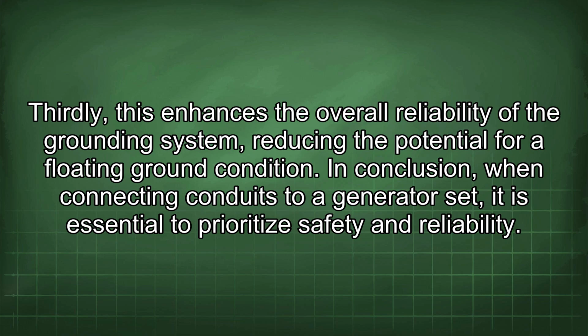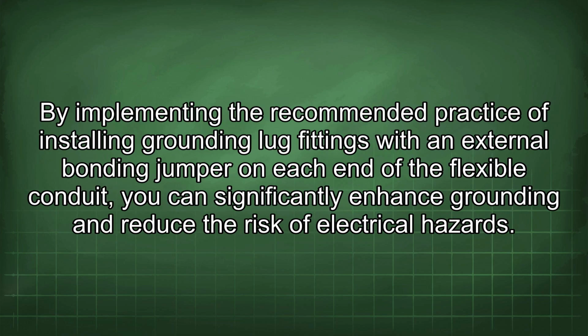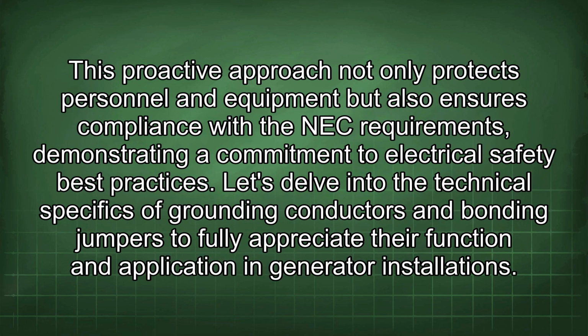In conclusion, when connecting conduits to a generator set, it is essential to prioritize safety and reliability. By implementing the recommended practice of installing grounding lug fittings with an external bonding jumper on each end of the flexible conduit, you can significantly enhance grounding and reduce the risk of electrical hazards. This proactive approach not only protects personnel and equipment but also ensures compliance with the NEC requirements, demonstrating a commitment to electrical safety best practices.